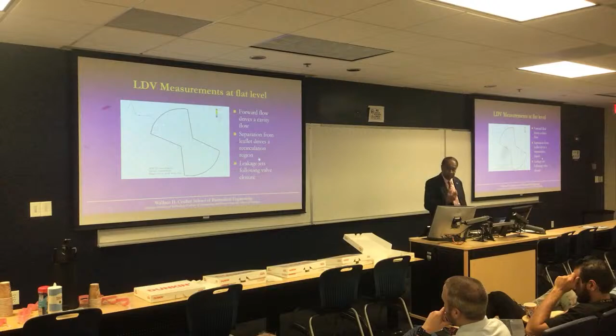So they built these. We didn't have their machine drawings. They had the machine drawings. They had these machined, very time consuming to create one of these models at that time. And then from these clear plastic models, we could look at flow through the hinge using laser Doppler velocimetry. And this allows us to look at flows through them. And I want to show one example where this type of analysis led to looking at the failure of a given valve.